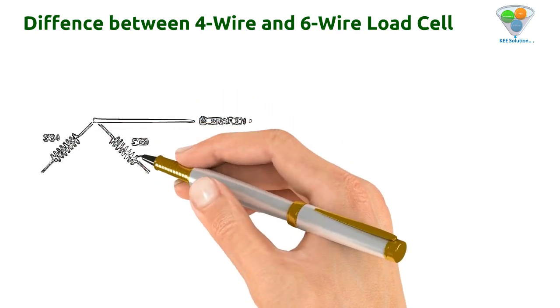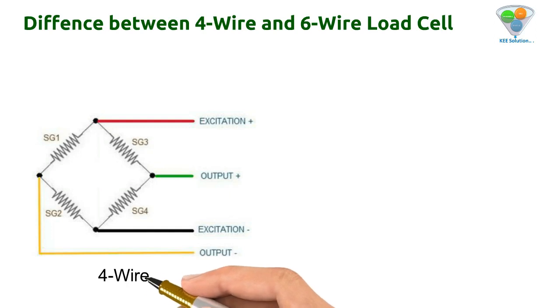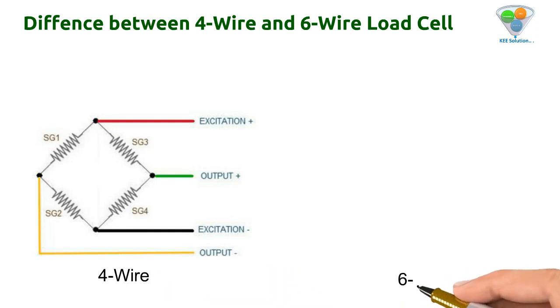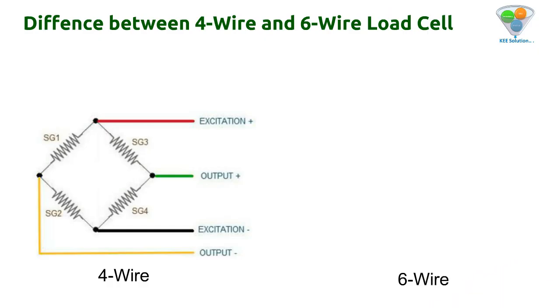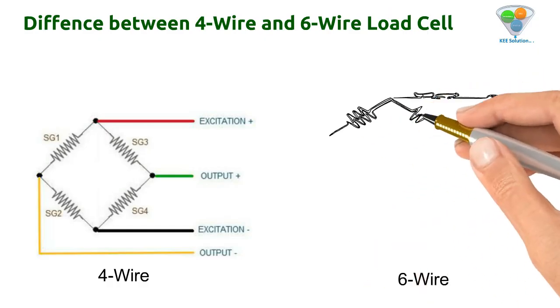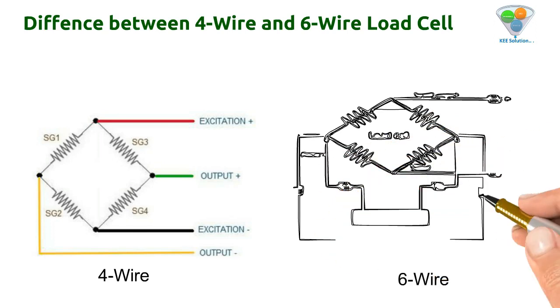The difference between a four-wire and six-wire load cell: in the four-wire bridge, SG1, 2, 3, 4 are the strain gauges. Excitation positive and negative are taken from the upper and lower ends of the bridge, and the output is taken from the sides. For the six-wire, the same four strain gauges are used but with two additional sensing signals in parallel with excitation.